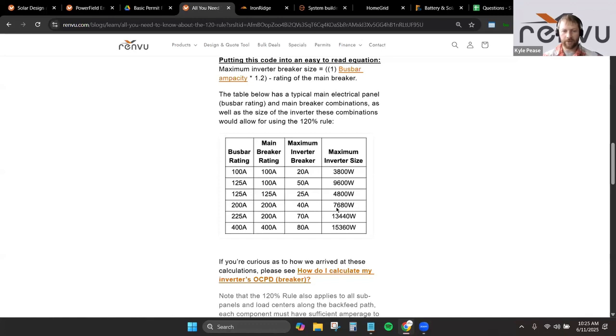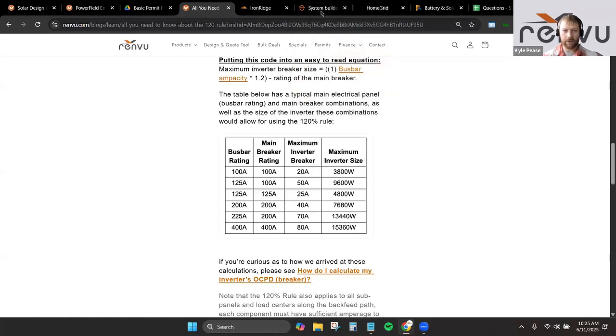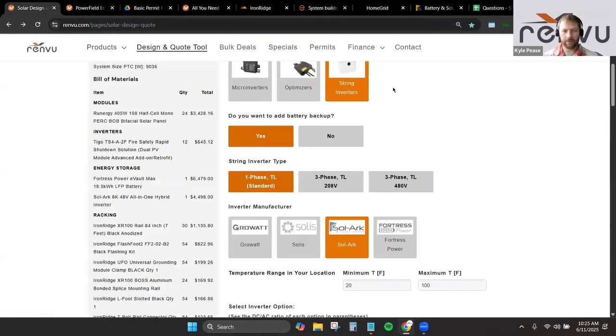So you can have an inverter of 7.68 kilowatts DC, so AC that's going to be 7.68 kilowatts with that 1.25 DC to AC ratio. You're going to be up around 9 kilowatts or so for your DC array. So with this example, looking at...